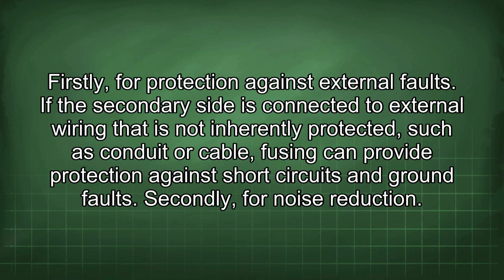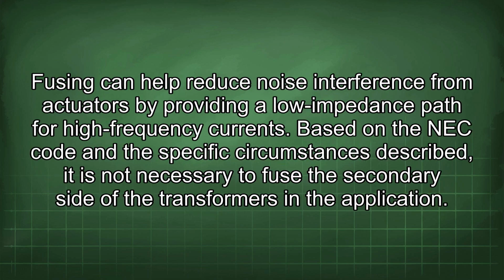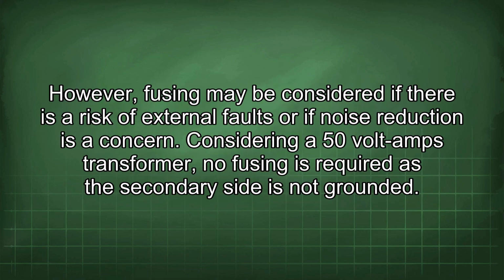If the secondary side is connected to external wiring that is not inherently protected, such as conduit or cable, fusing can provide protection against short circuits and ground faults. Secondly, for noise reduction. Fusing can help reduce noise interference from actuators by providing a low impedance path for high-frequency currents. Based on the NEC code and the specific circumstances described, it is not necessary to fuse the secondary side of the transformers in the application. However, fusing may be considered if there is a risk of external faults or if noise reduction is a concern.